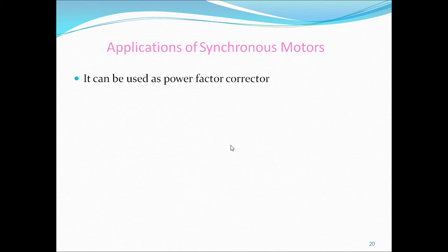If you see the applications of a synchronous motor, it is used for power factor correction. As we said, it works at both lagging and leading power factor. If you go to any big industry, all industries have very big induction motors, and as we know, all induction motors run at a lagging power factor only.